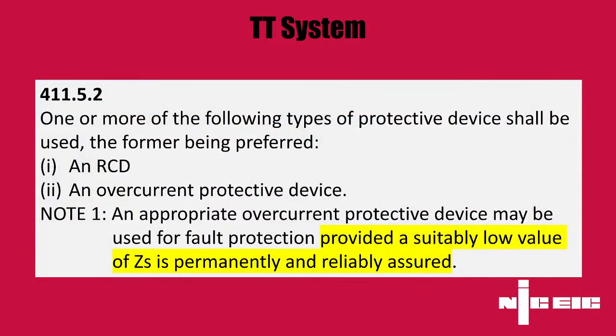So, yeah, absolutely. If we just show the audience that regulation again, and as you said, this is the section for TT systems. One or more of the following types of protective device shall be used, the former being preferred, and then it gives us an RCD or an overcurrent protective device. And again, as you said, the note informs us that an appropriate overcurrent protective device may be used for fault protection, which is exactly what the question was asking, but it goes on to say provided a suitably low value of Zs is permanently and reliably assured.